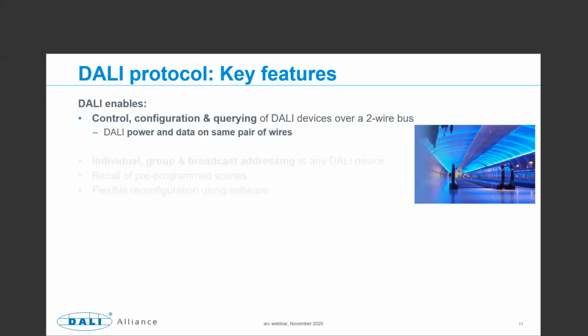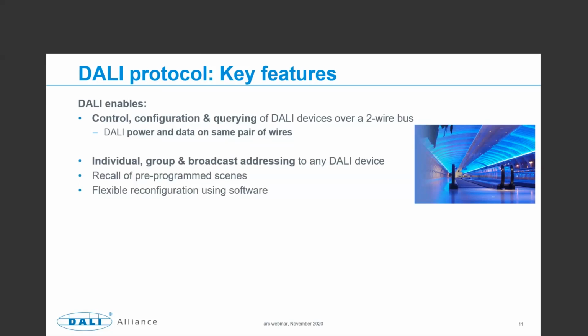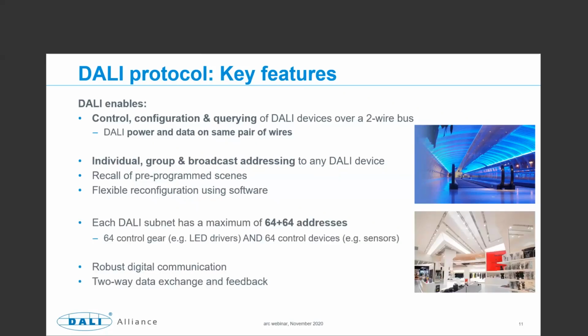Each DALI subnet has a maximum of 64 plus 64 addresses. And it's written in this way because you can have 64 control gear, such as LED drivers, and 64 control devices, such as the sensors. And it provides robust digital communication. The communication signaling rate is relatively slow deliberately to ensure it's robust, but due to the very efficient use of the commands and addressing schemes, typically you only need 1 or 2 commands to affect all of your lighting system. So it's fast, efficient, and robust.